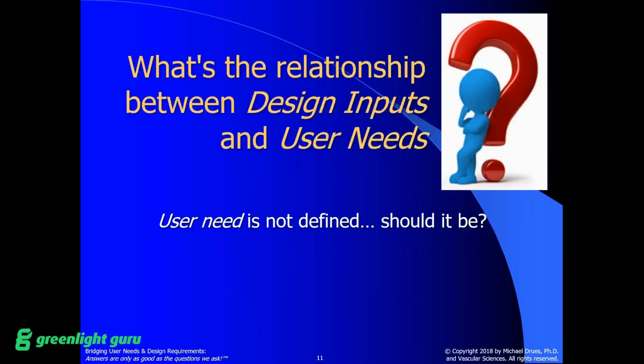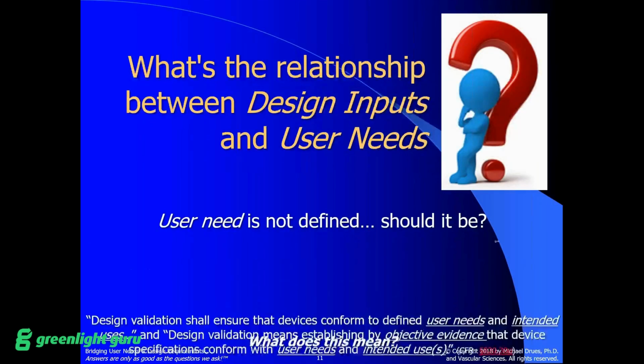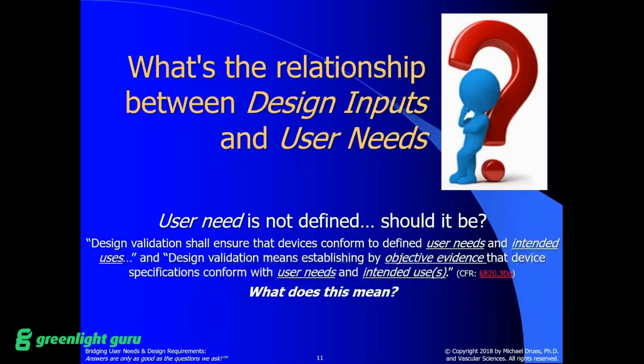So in the regulation, I just shared with you the definition of a design input. Interestingly enough, there is no definition for a user need. Should there be? Well, perhaps some people might think so, but I would say not. Here's the closest thing in the regulation that we have. This is part of design validation. Design validation shall ensure that devices conform to defined user needs and intended uses. We've talked about intended use, but not user needs very much yet. And design validation means establishing by objective evidence, whatever that means, objective evidence, that the device specifications conform with the user needs and the intended uses.